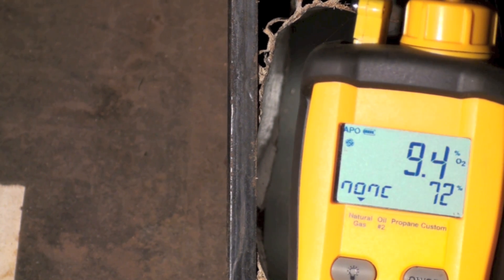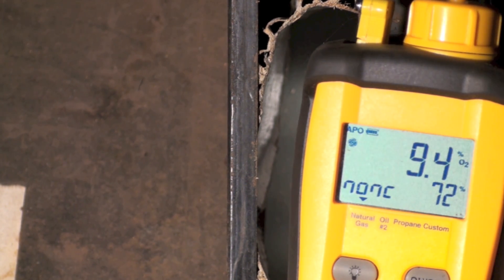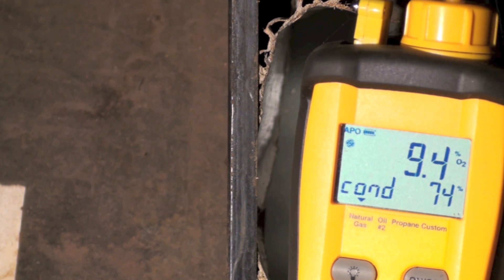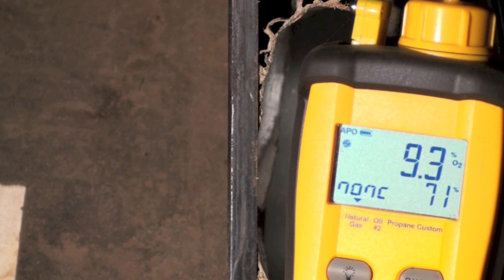Let's look at the O2 and CO2. CO2 is 6.4, O2 is 9.4. And non-condensing, now I'm showing 71. So even though I reduced the gas flow to the burners, I did not make this furnace more efficient. I actually probably made it a little less efficient.